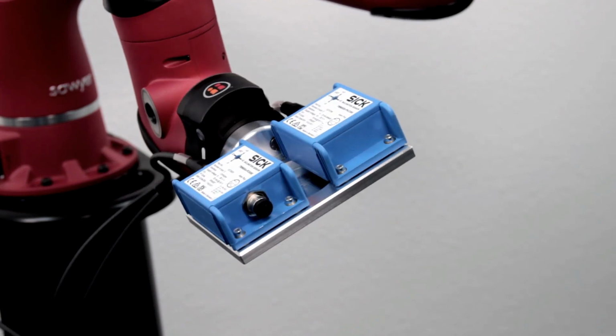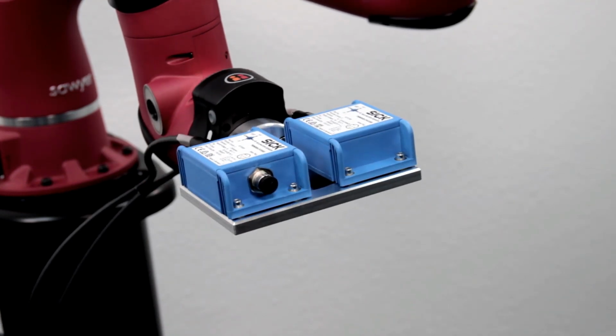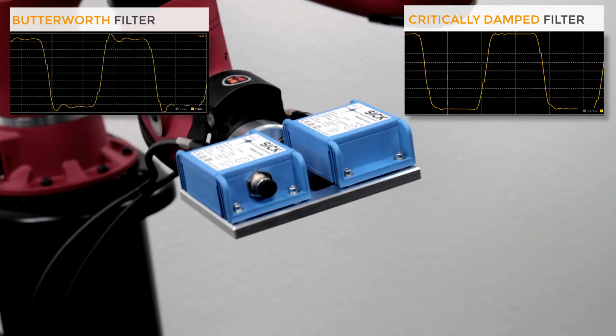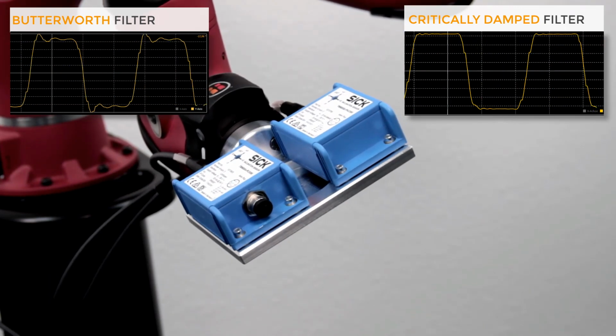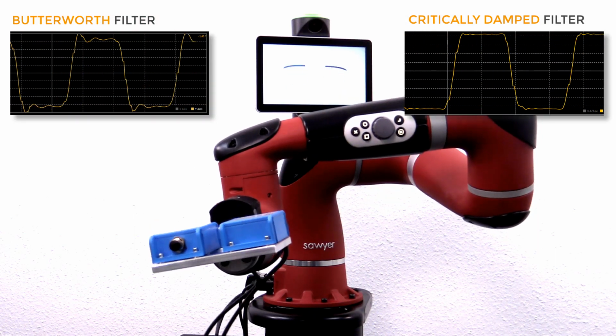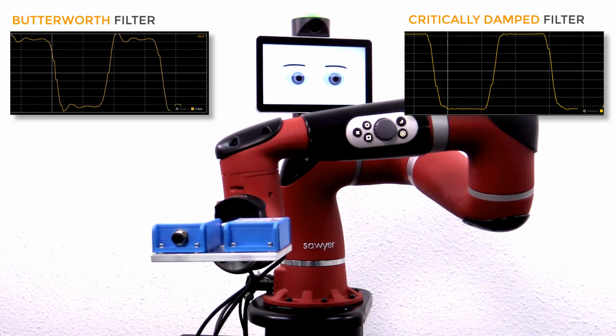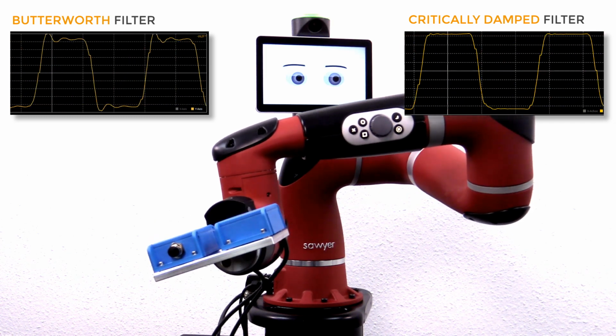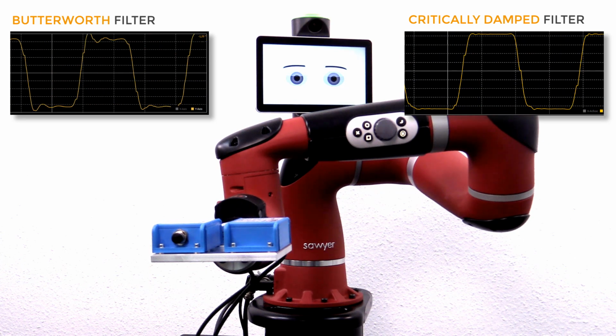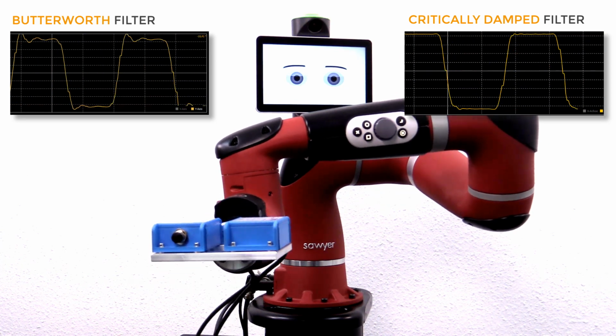To demonstrate the different filter characteristics, two inclination sensors with two different filter settings will be moved by the same robot arm at the same time. As you can see, the critically damped filter results in a faster signal answer without any overshoot and better vibration compensation in comparison to the Butterworth filter.